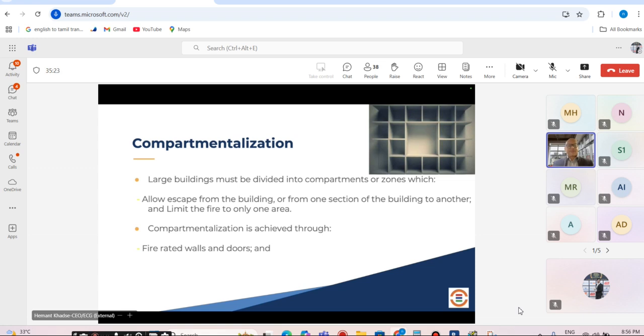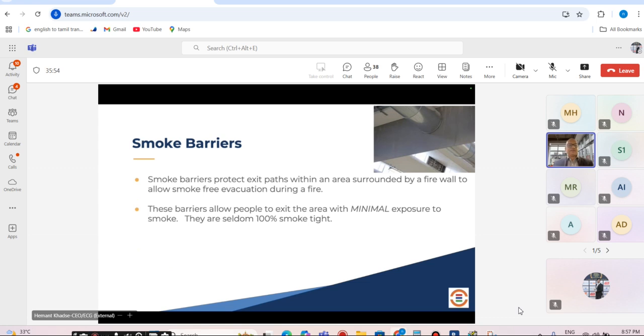There are various means of achieving compartmentation. It could be by using fire curtains or water curtains, fire rated walls, fire doors. So compartmentation essentially becomes an important part of your life safety design at the construction level, where you are ensuring the life safety and even the smoke management per se, because it is ultimately protecting your egress path so that your evacuation becomes very safe.